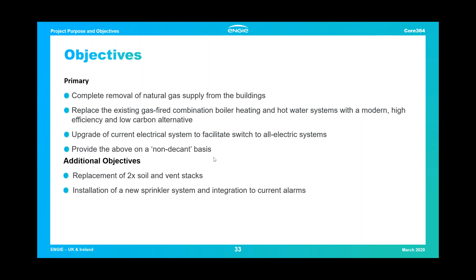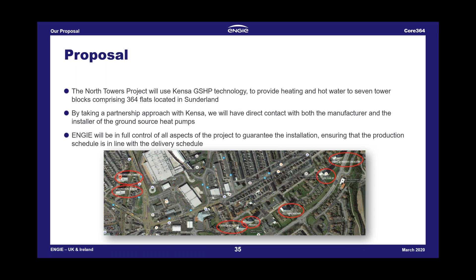So the proposal covered 7 tower blocks, spread across the north banks of the River Wear, providing ground source heat pumps through district heating for each site. There were 5 sites housing 7 tower blocks, each taking its own communal heat pump with extraction and discharge wells to deliver district heating throughout the buildings, leading to individual Kensa heat pumps, which Stuart will give more technical detail on later.